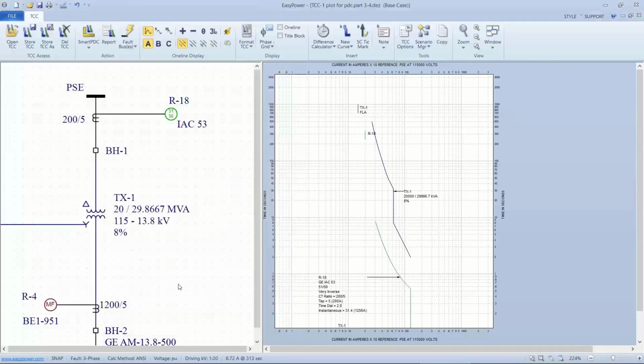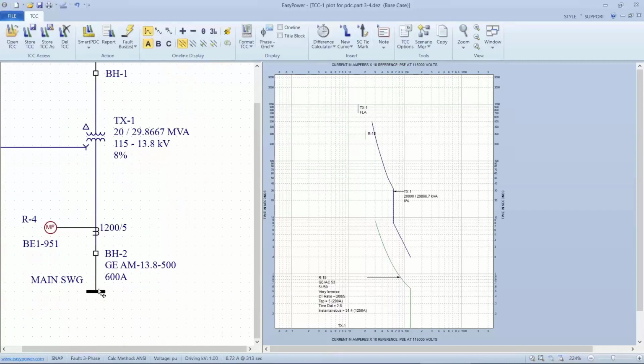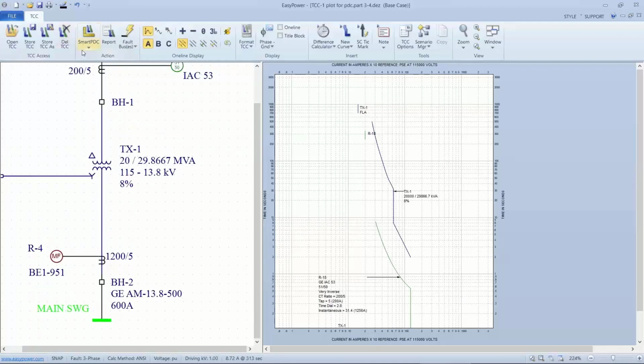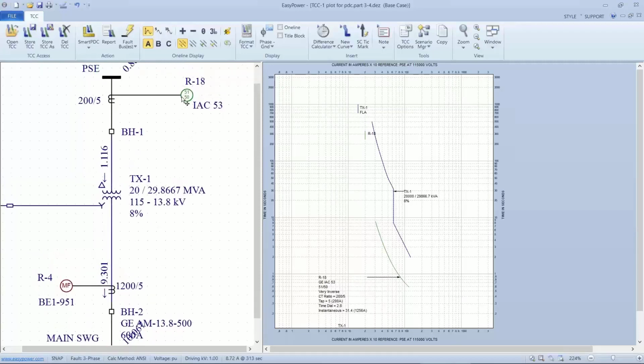Now we do have an instantaneous setting. Let's go back and talk about that for a second. If I come down here and fault this bus, this is the worst case fault that this transformer will ever see in normal conditions. In other words, we have a hard fault in the secondary of the transformer. When we fault this particular bus, we see just over 1116 amps will be the worst current that this system will see. So we can set our instantaneous plot slightly above this. 1116 amps, we're going to go for something near 1200.